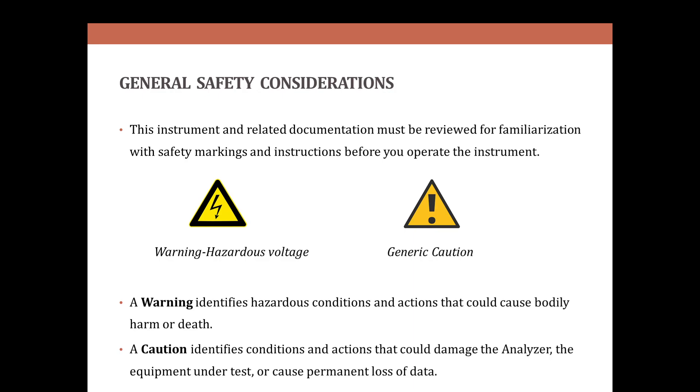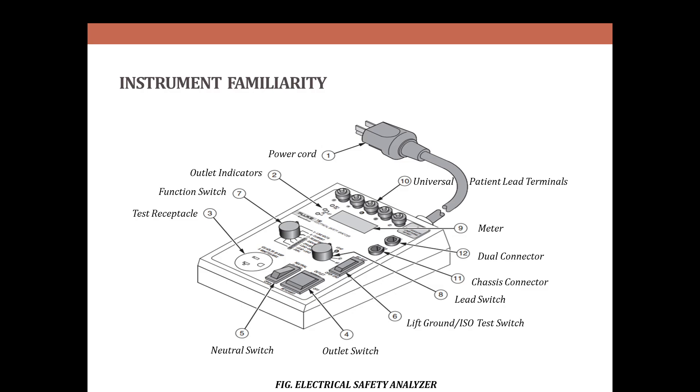For instrument familiarity, this is the analyzer which is used to test other instruments and equipment. Here the power cord supplies the power to the electrical safety analyzer and to the device which are under test. The measurement circuits are energized with the power cord which is plugged into an outlet.